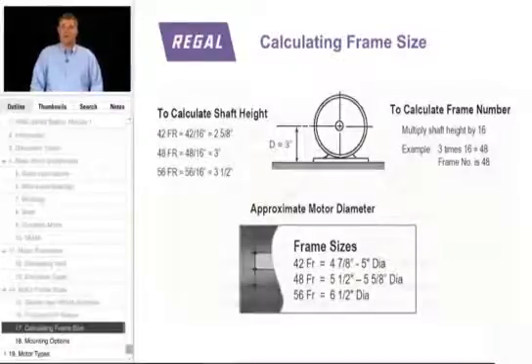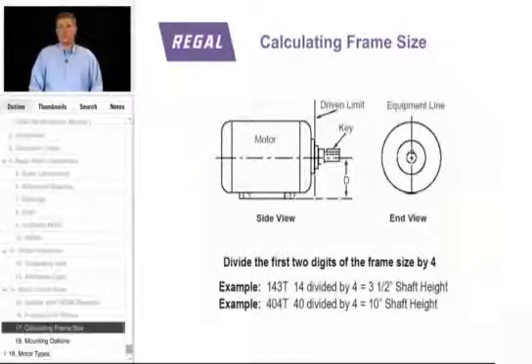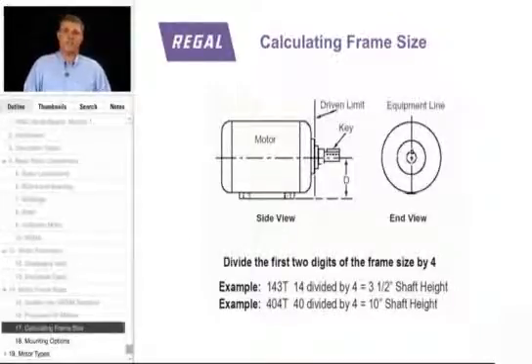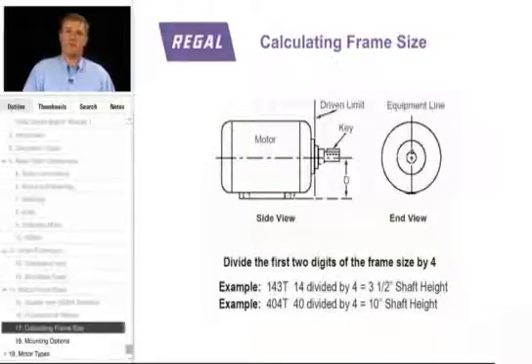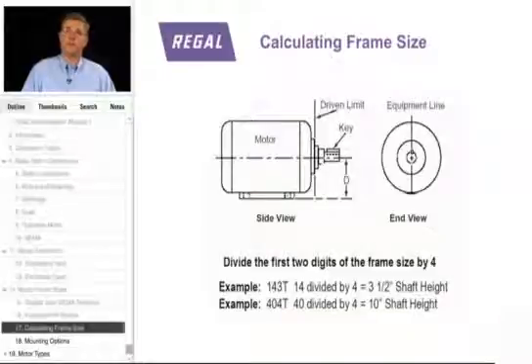On the larger NEMA T frame motors, 143 T and larger, these motors also tell us center of shaft but no longer in 16ths of an inch. It's the first two digits of the frame size divided by 4. So a 143 T frame motor — 14 divided by 4 — is 3 and a half inches. So we can determine the center of shaft by using that frame size.